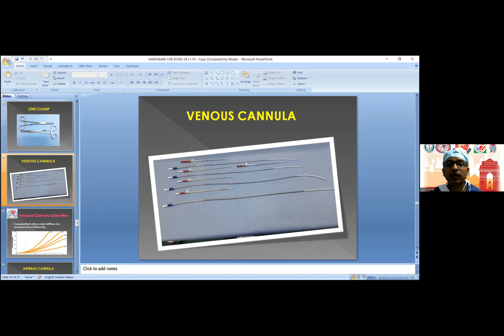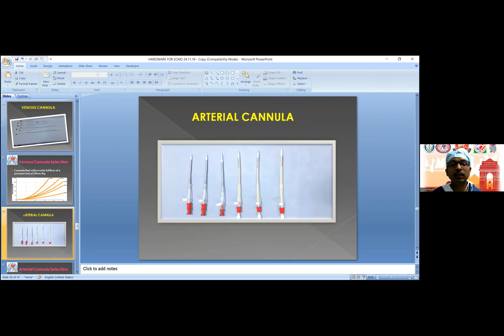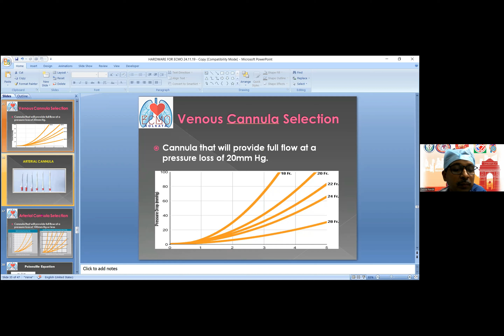One is for the drainage system, which we still tend to call the venous cannula, and the other is the arterial cannula, chosen with the criteria from the manufacturer's literature. For 3 liters of flow, the pressure drop should be about 20 millimeters for the drainage cannula, and for the arterial return cannula we can accept a maximum of around 50 to 100 millimeters of mercury.